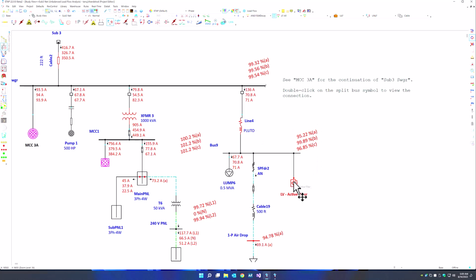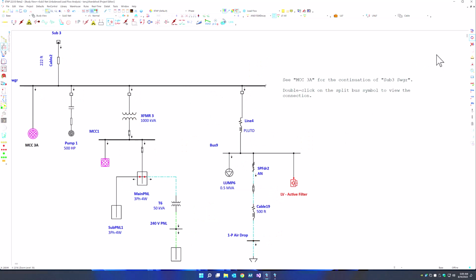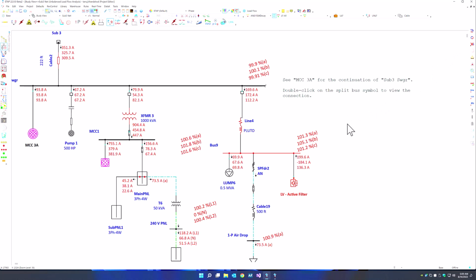The active filter is currently turned off. We can simply go in, turn on the power factor and load balancing mode, and rerun the power flow again. And essentially ETAP will use the active filter, inject the ABC current flows such that cable 2 is balanced as close as possible. And this is being done with respect to the overall rating of the active filter.